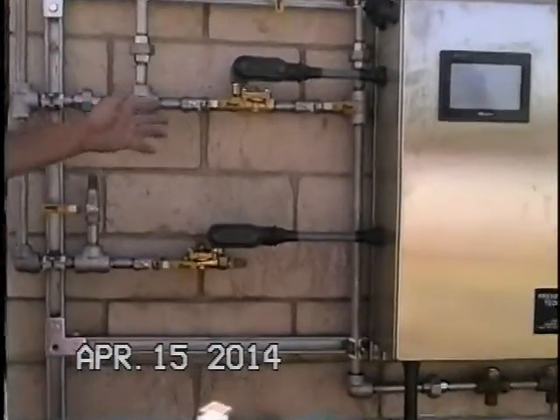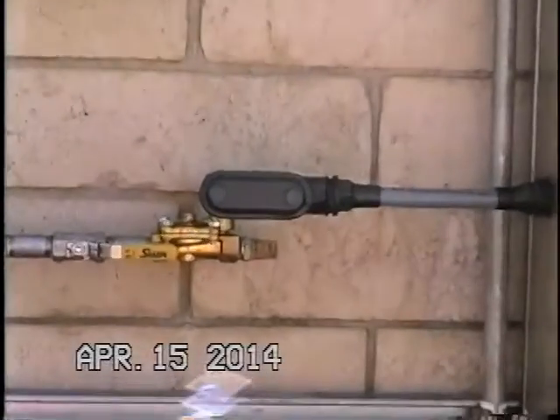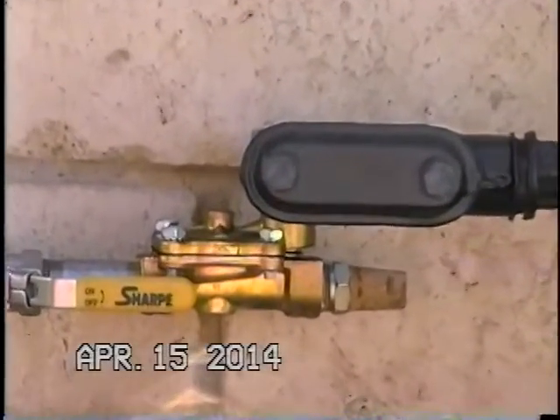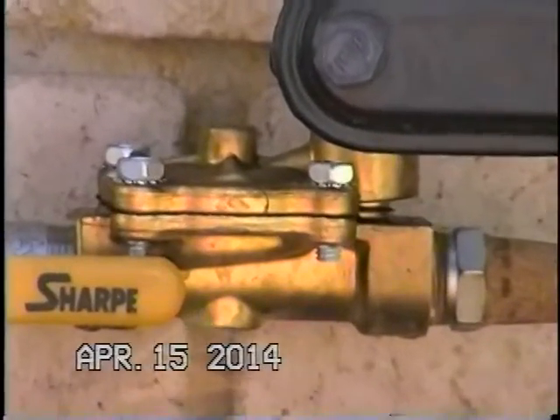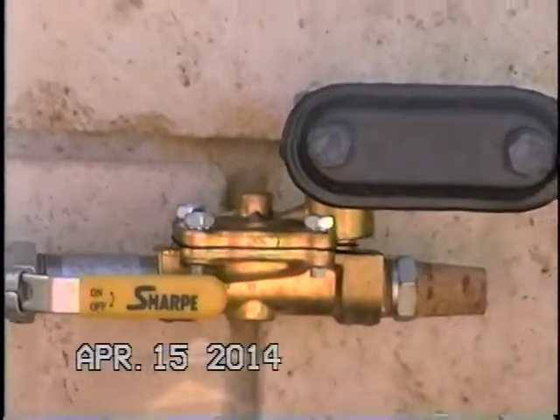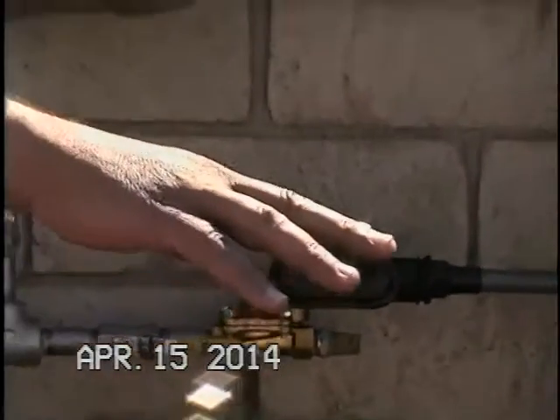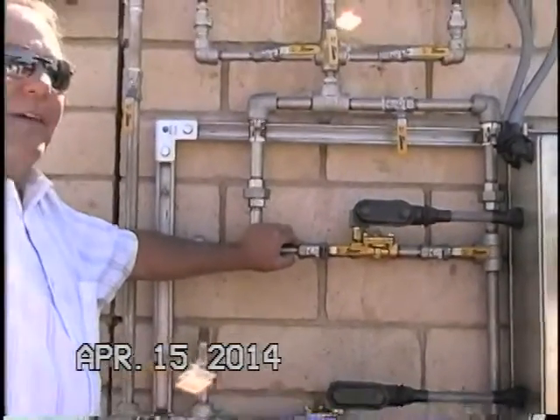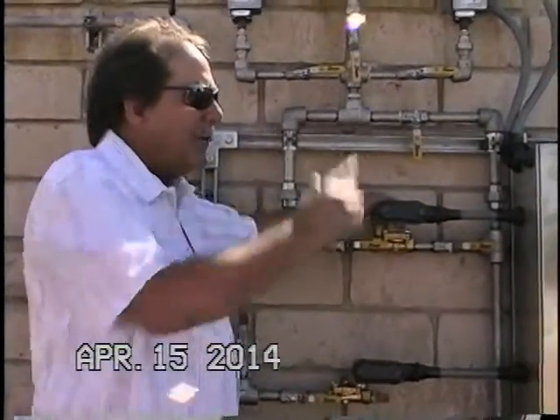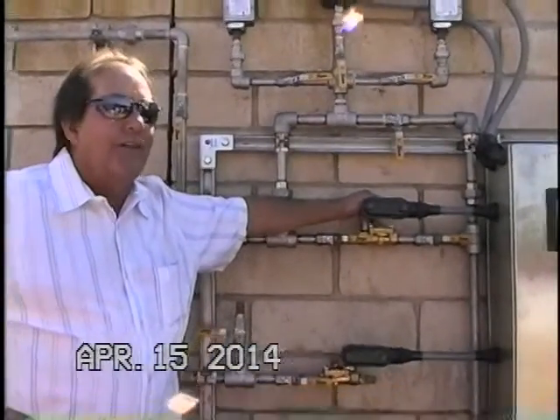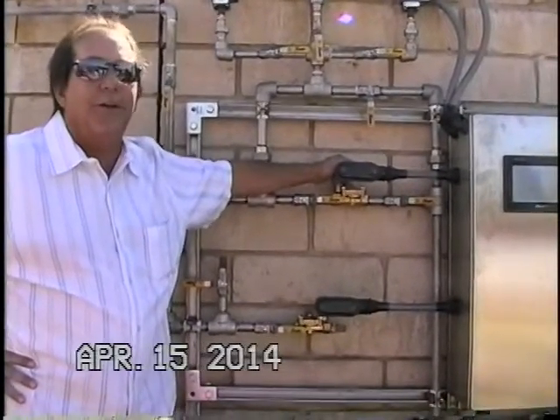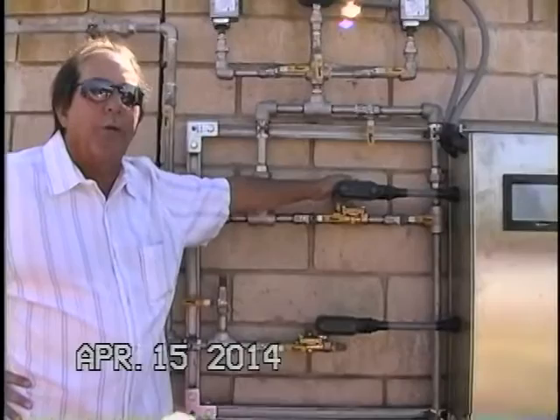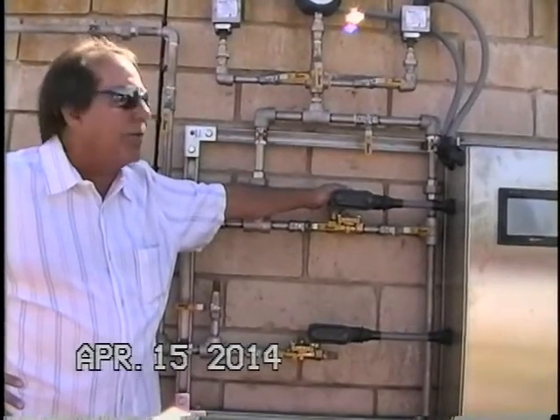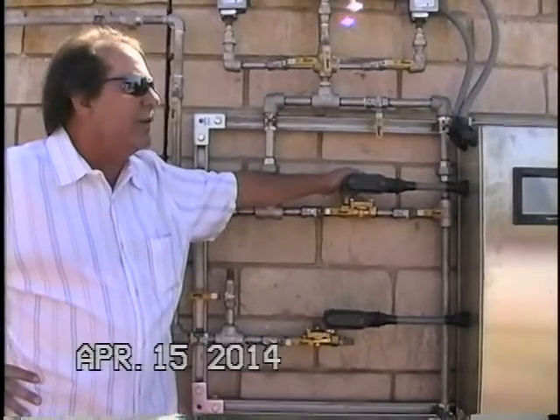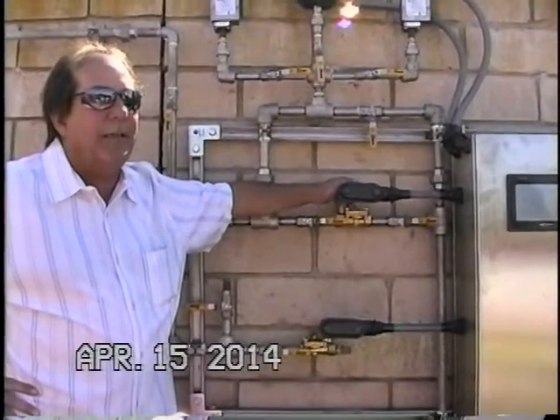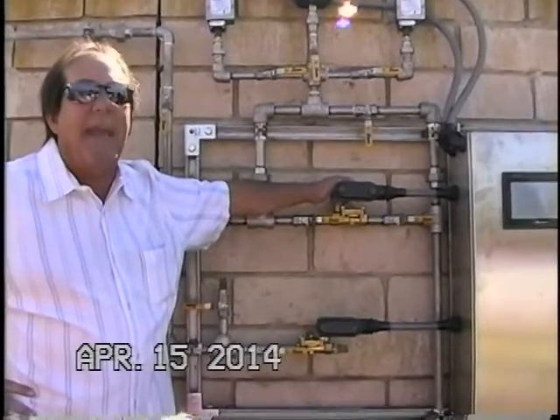I've seen a condition up in Vegas, where it's really hot, we do a lot up there, that the guys shut the pump station down. They forgot to shut down the surge tank. We were in an add air condition, and the solenoid just stayed hot. The compressor wasn't running, and it just stays actuated for days and days and days at 120 degrees, and I've seen the coils burn up. But they're easily replaced by ASCO. There's a lot of ASCO dealers around. It's readily available. So typically you could get it within 1 day and replace it the same day.